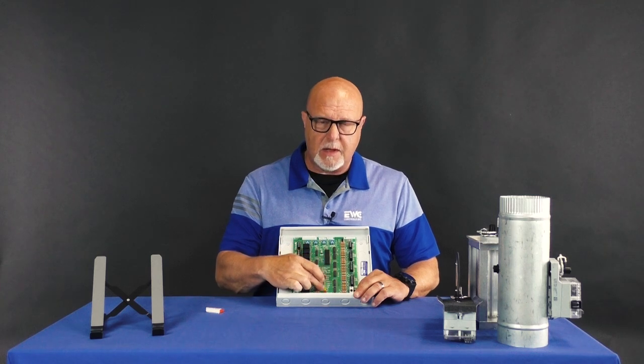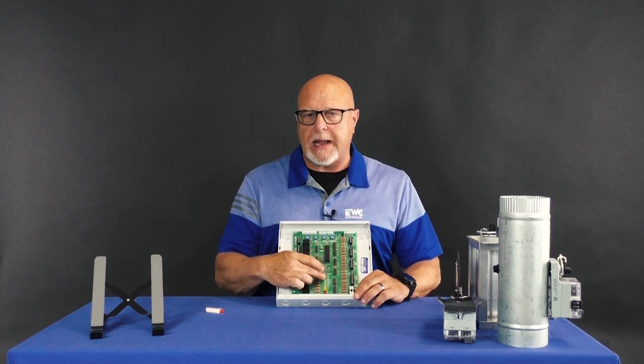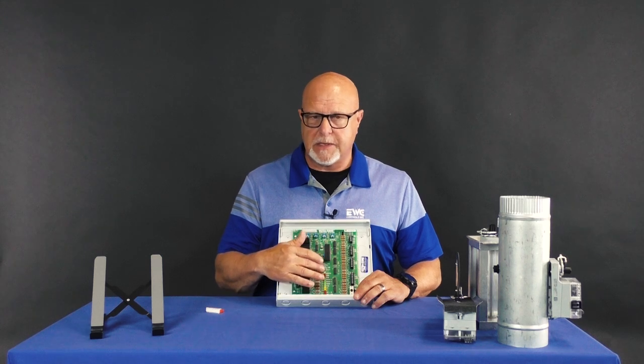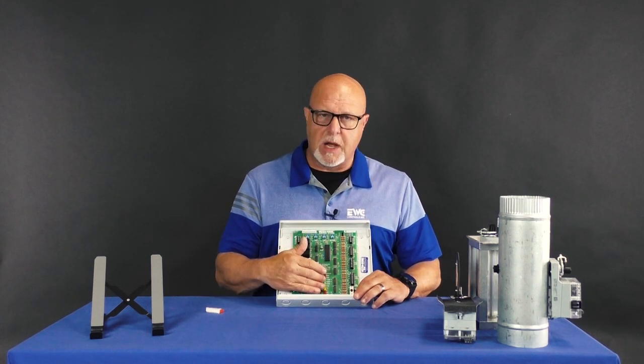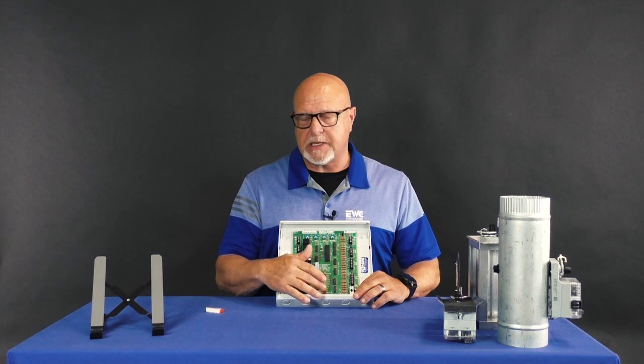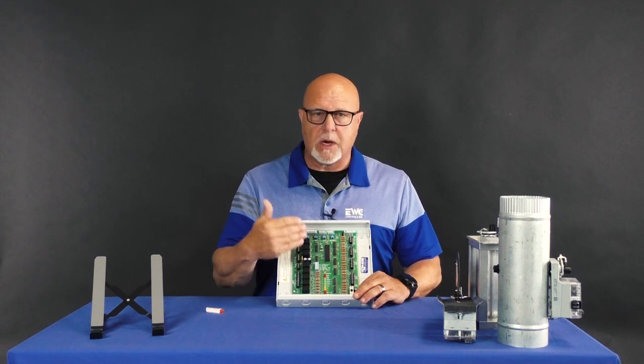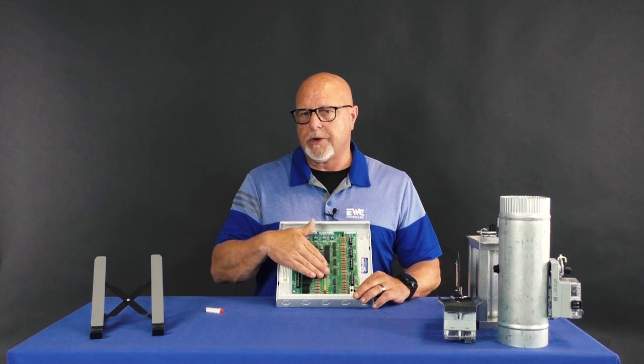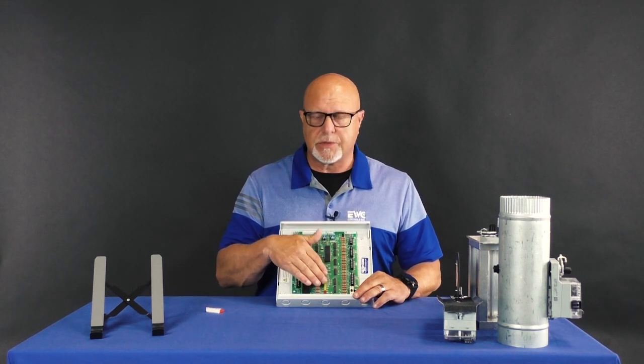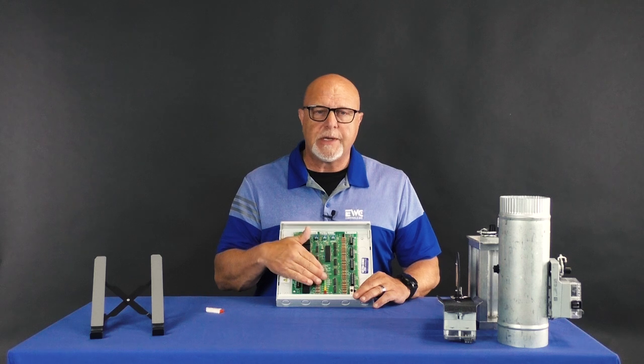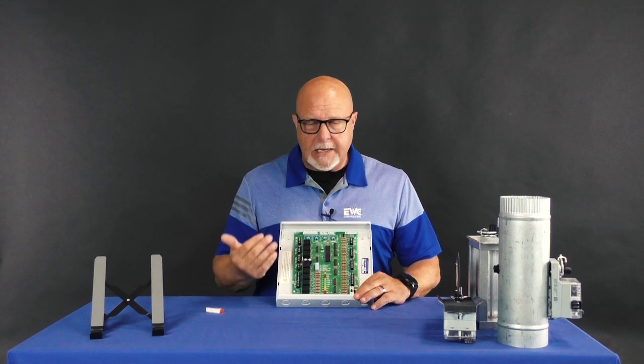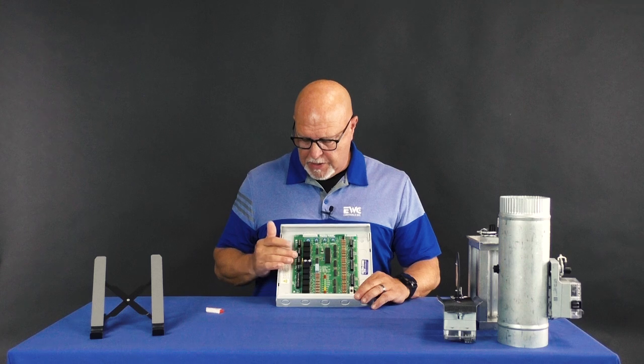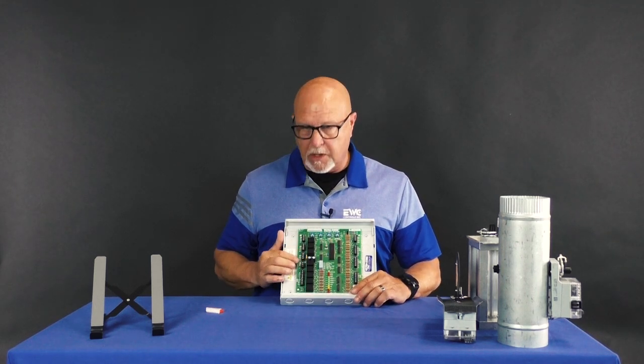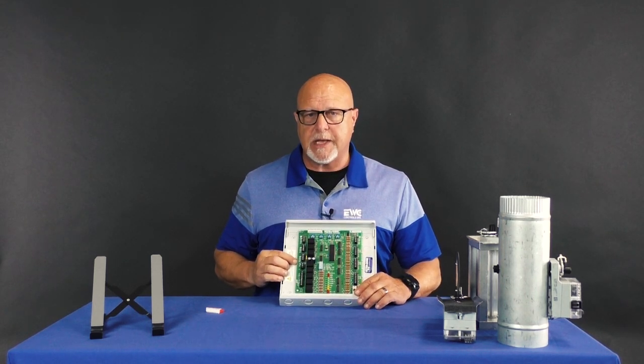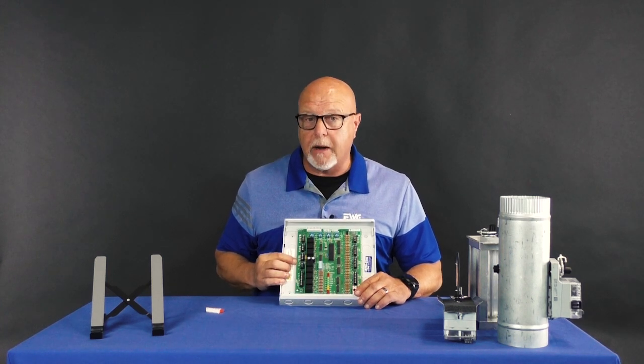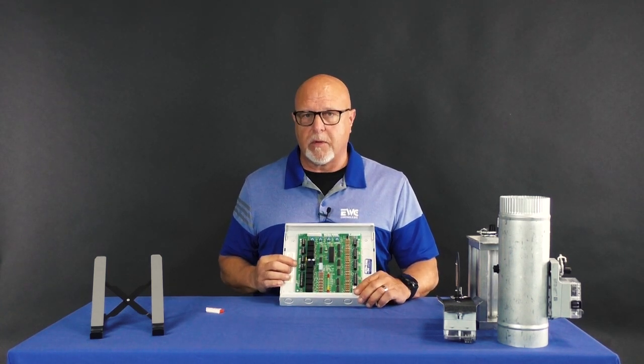You also have many LED lights to give you a diagnostic tool to tell whether or not something is operating, what zone is calling, what zones are not calling. Am I in first stage or second stage? Do I have a Y1 call? Do I have a W1 call? All of those are directly in line with the coil relay on your furnace or air handler. Very good diagnostic tools. Any thermostat can be used. Like I said before, your damper terminal blocks on the BM Plus are set up to be able to handle 2-wire and 3-wire power open, power closed dampers.